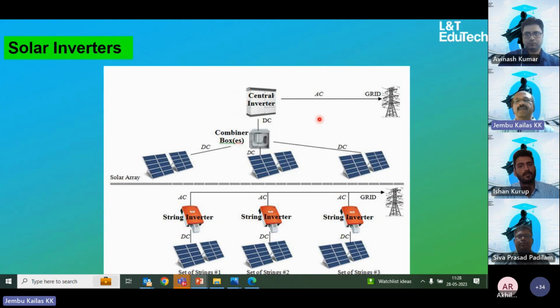So also it takes care of the grid changes actually. Grid voltage fluctuations, grid voltage, even the frequency changes, everything. Accordingly, this inverter will adjust its output, so that it will always be synchronized with the system. Unless there is a major fault, this inverter will always try to synchronize with the grid. So you should understand one thing, that this is not producing like a black start kind of thing. You have to take the power supply from the grid, and this central inverter will synchronize with the grid voltage actually.